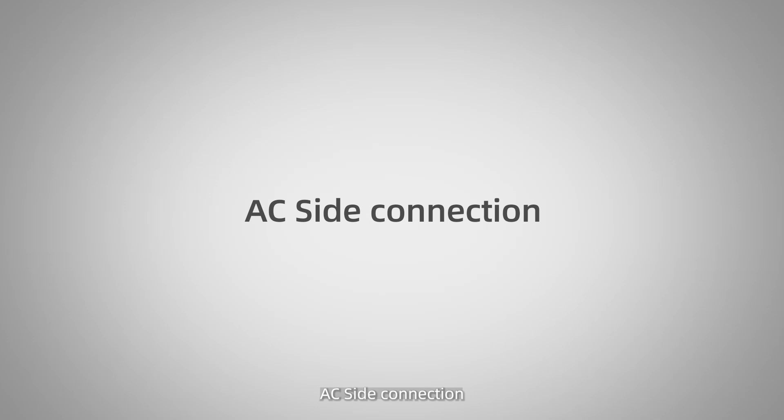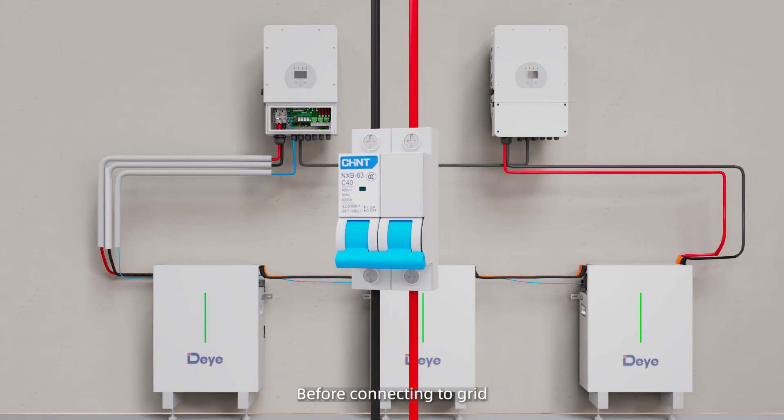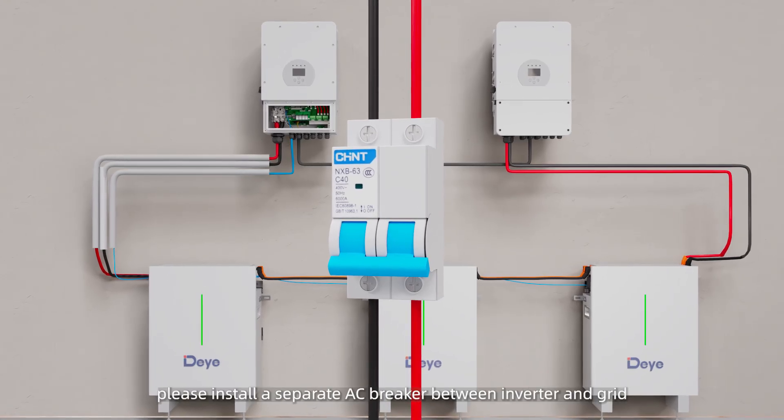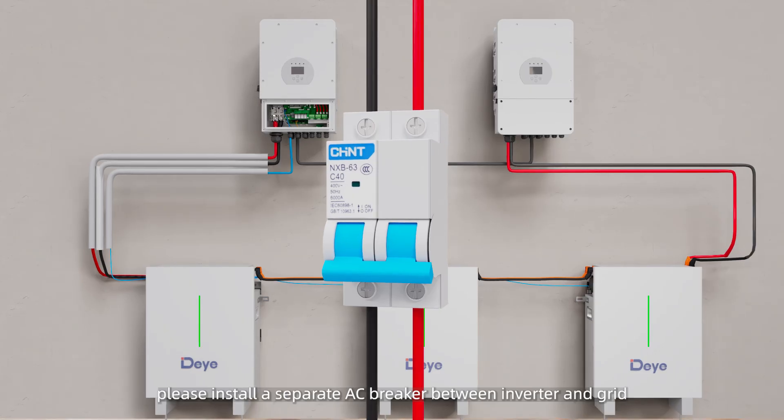AC side connection. Before connecting to grid, please install a separate AC breaker between inverter and grid. It is also recommended to install an AC breaker between backup load and inverter.